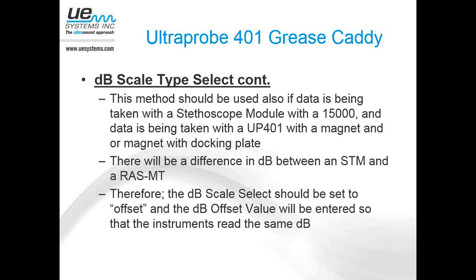So again, in this case, you would go into the dB scale type select, change it from relative to offset, and then you would go into the next menu and set your dB offset value to whatever that difference is. So that way, again, both instruments are going to read the same dB.